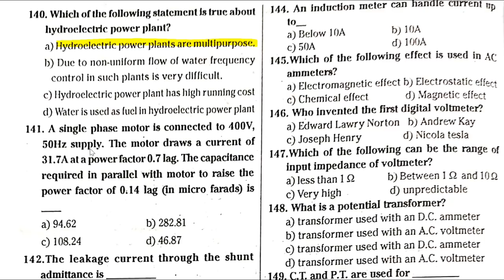A single phase motor is connected to a 400 volt, 50Hz supply. The motor draws a current of 31.7 amperes at a power factor of 0.7 lag. Find the capacitance required in parallel with the motor to raise the power factor to 0.14 lag, in microfarads. Options: 94.62, 282.81, 108.24, 46.87. The answer is 94.62. This problem requires a calculator, but you may not find such a question in the examination.